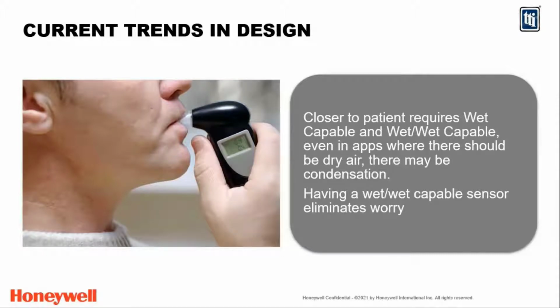It also speeds up the response time so that they can change your decision making. If you have to wait for the pneumatics to change or your air pressure to change there by the patient breathing, and you have to wait 6 feet worth of tubing to get that answer, you're talking milliseconds, and you could have used that time to make your decision as to whether to increase the oxygen or whatever course of action you're going to take. So it's not as accurate if you do it inside the equipment as it is at the patient.